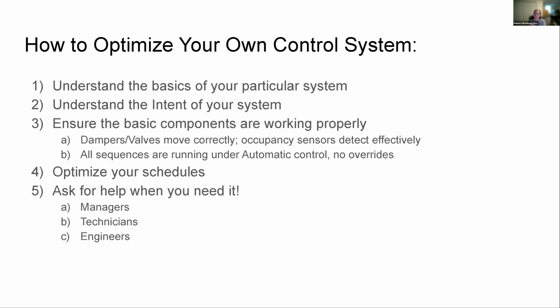So if you have a VFD that's in hand, or a damper overridden on your air handler so that it's always open or closed, there was a problem that was being fixed by that, but long term it's going to cause the system to not operate optimally. Everybody knows you've got schedules in your building—this is another point where overrides sometimes come into play. Hey, we've got a weekend event in the gymnasium, could you make sure the lights are on? Sure, quick exception or override, and away we go. But again, we have to come back and make sure those are cleared out. And building usage changes, so make sure your schedule matches the use of the building.